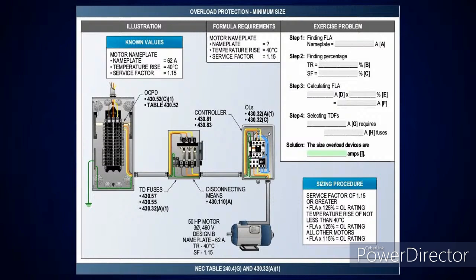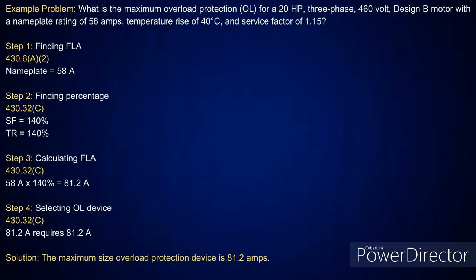Now, this one is where you're going to get into the maximum, and you're just going to come down and look at 430.32(C). When you pick it up, you're going to see the same layout right after the text. Then you're going to have your service factor at 1.15 or greater, that's 140%. If it's 40 degrees C or less, 140%. If it doesn't meet both of those, then you go at 130%.